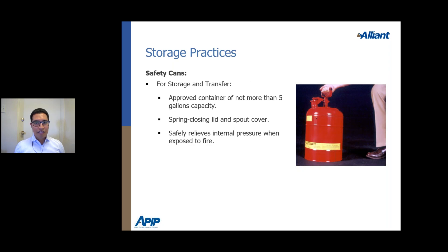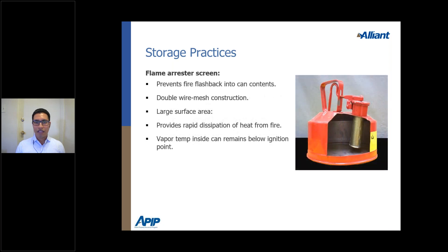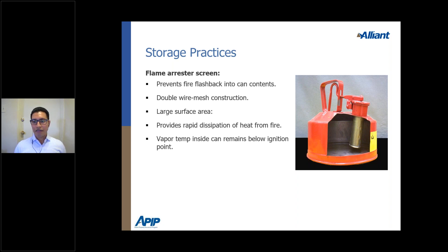Safety cans for transferring and storing gas have specific requirements: the lid should be spring-closed, and there should be a safety relief for internal pressure when exposed to fire. They should also have a flame arrestor screen — sometimes wire mesh or other mesh construction — which prevents a fire flashback into the contents from releasing from the container.